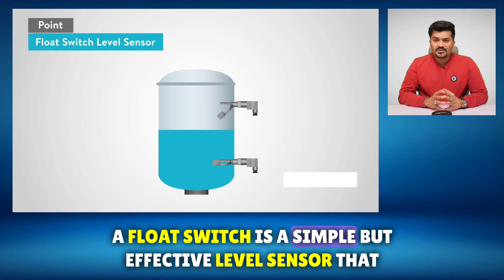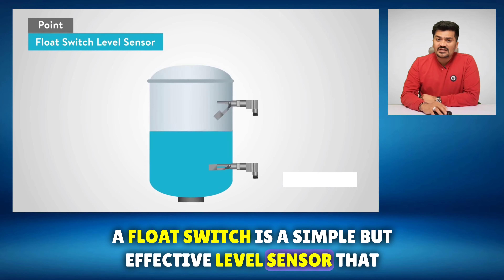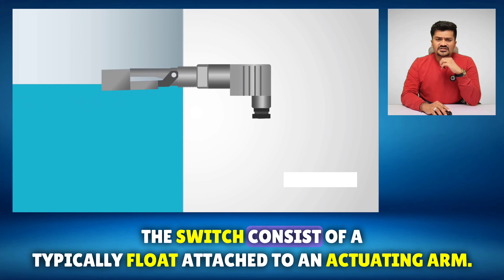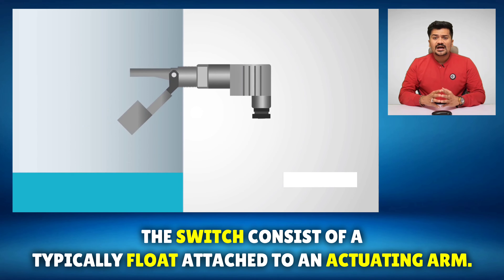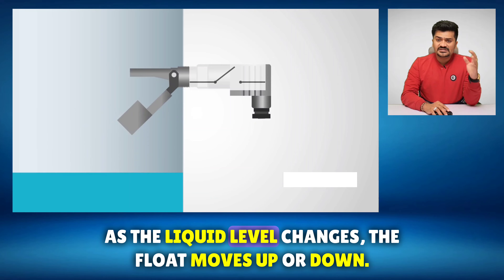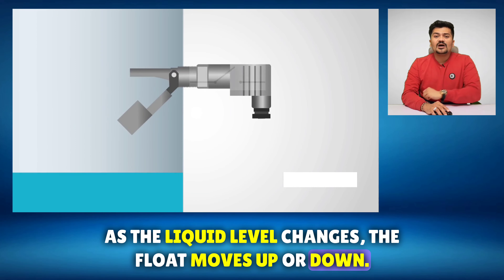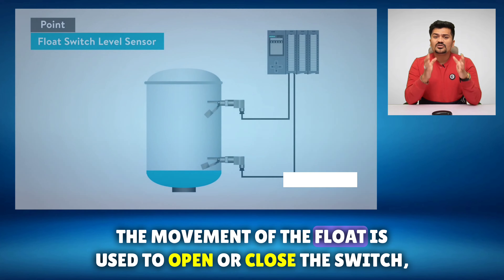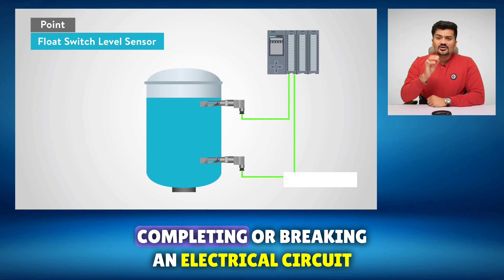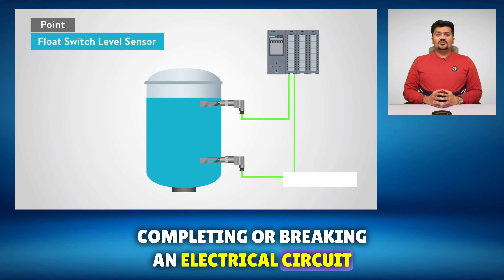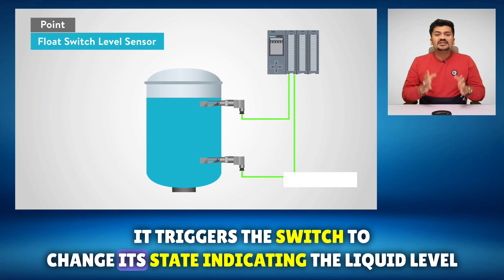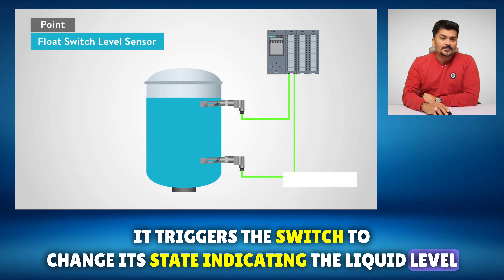A float switch is a simple but effective level sensor. The switch consists of a float attached to an actuating arm. As the liquid level changes, the float moves up or down. The movement of the float is used to open or close the switch, completing or breaking an electrical circuit. When the float is at a certain level, it triggers the switch to change its state, indicating the liquid level.